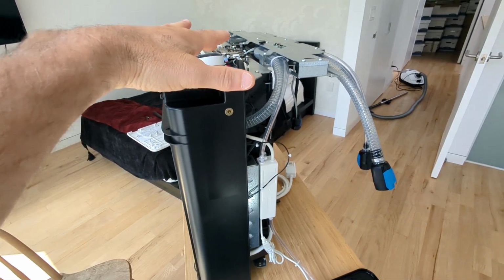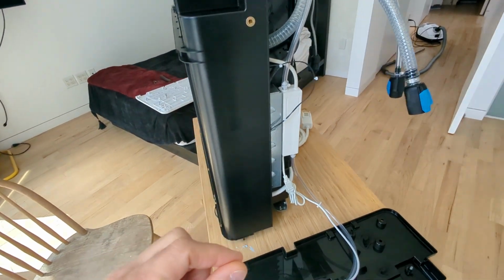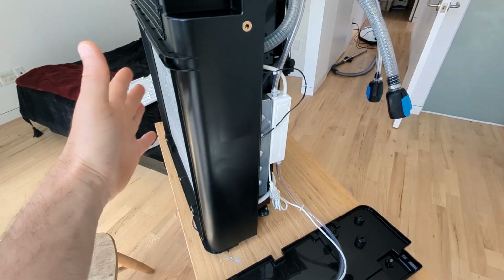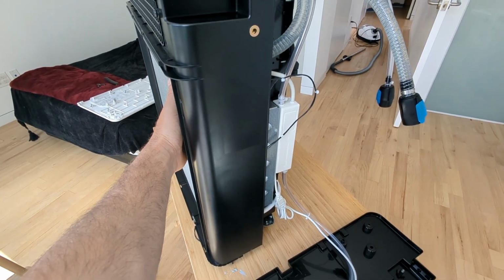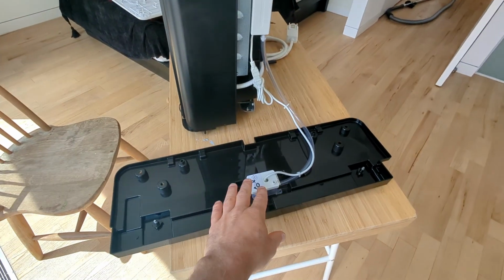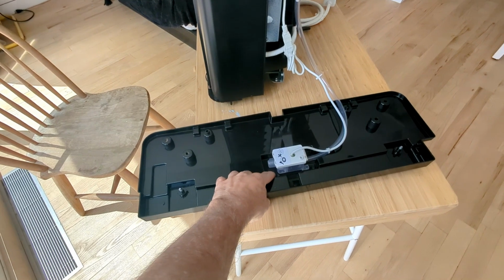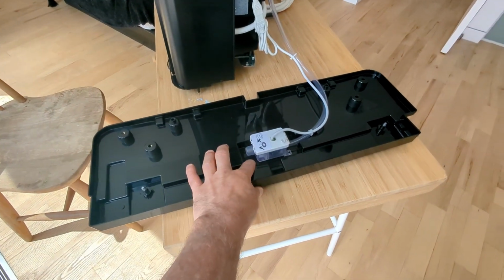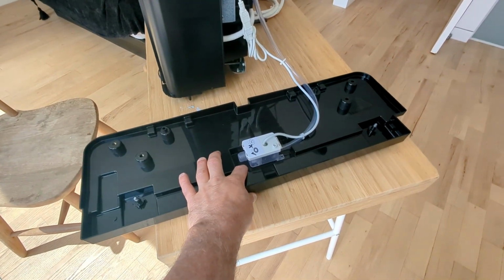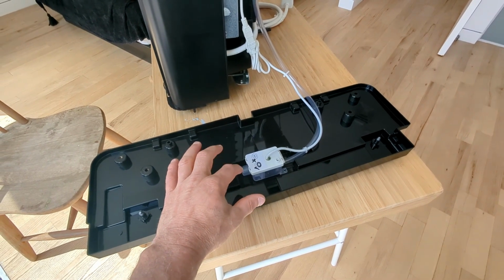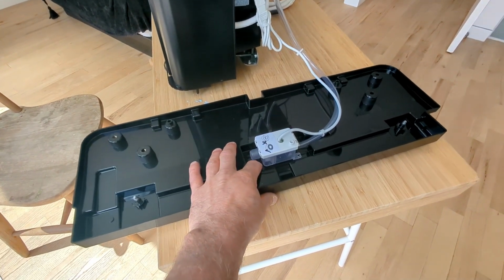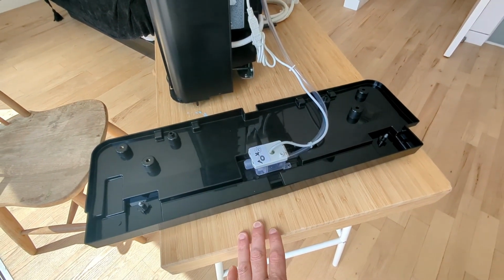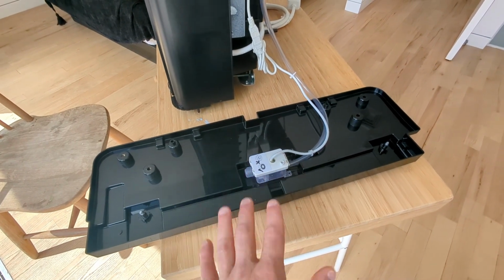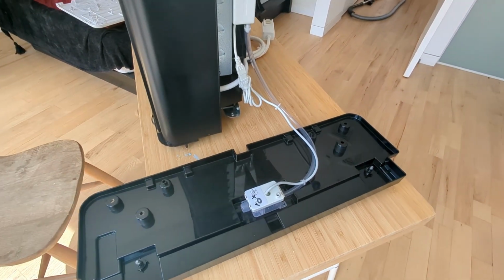There's enough smarts in that controller that they could have done something, like waiting a few minutes after you stop running the evaporator fan and then running this pump prophylactically to drain out any water that has collected, even though it wasn't enough to trigger it yet. That way you have the least amount of time water sits stagnant in this tray, and you really can reduce the chance of growing that slime, or at least have less of it.